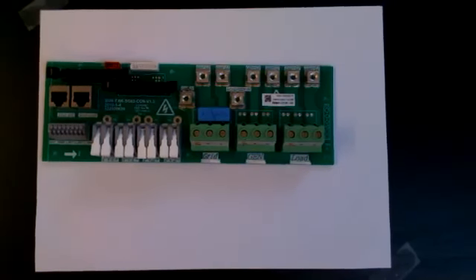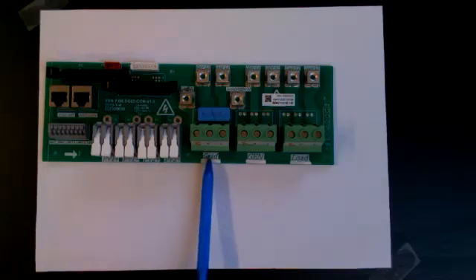But you also have to consider power balancing, because what you don't want to do is have any big, heavy air conditioners and stuff connected here, because you get a huge inrush current. And often when you switch an air conditioner off and you switch it back on again, there is a massive inrush current, and that inrush current can cause an overload. It's not a fault on the product. It's just purely because of an old air conditioner. So always remember that. So if you've got big old ones, connect them on the grid.